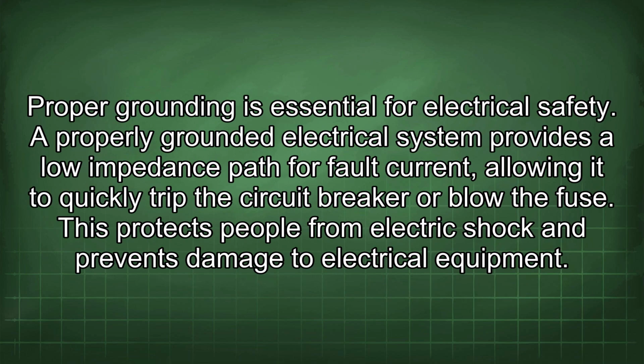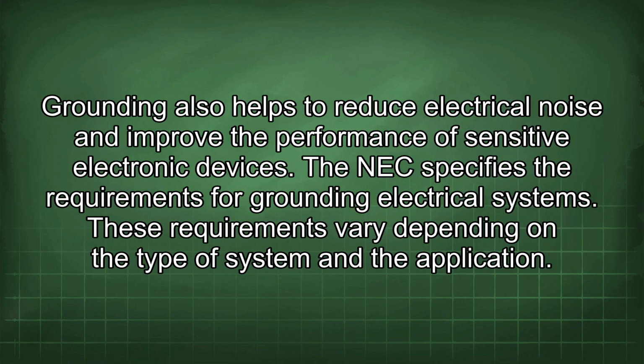Proper grounding is essential for electrical safety. A properly grounded electrical system provides a low impedance path for fault current, allowing it to quickly trip the circuit breaker or blow the fuse. This protects people from electric shock and prevents damage to electrical equipment. Grounding also helps to reduce electrical noise and improve the performance of sensitive electronic devices.